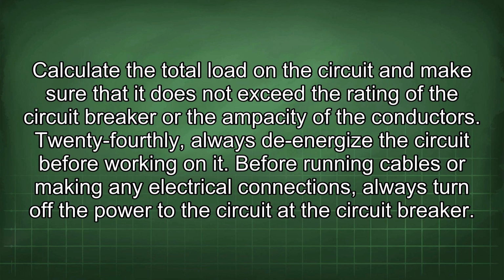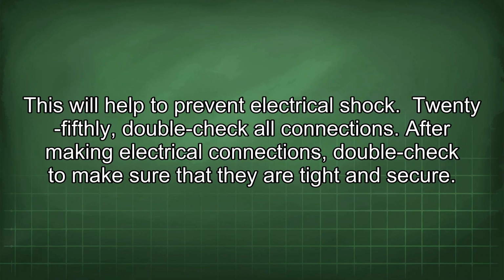Calculate the total load in the circuit and make sure that it does not exceed the rating of the circuit breaker or the ampacity of the conductors. 24thly, always de-energize the circuit before working on it. Before running cables or making any electrical connections, always turn off the power to the circuit at the circuit breaker. This will help to prevent electrical shock.